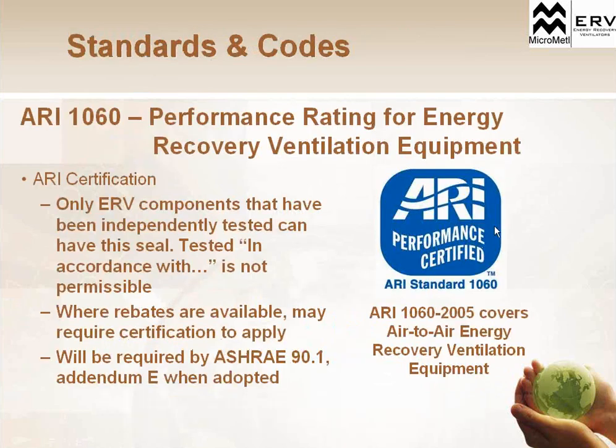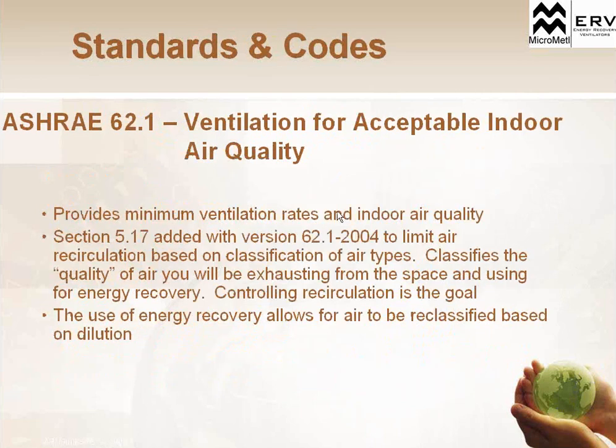Some of the other standards and codes, we've talked about the layout of the system, the ERV unit itself. ERVs are regulated by ARI 1060. It's that performance rating for ERV equipment. Only ERV components that have been independently tested can actually have this seal. So if you are purchasing ERV equipment, look for that ARI performance certified standard on all your ERV equipment. That is the rating firm for ERVs.